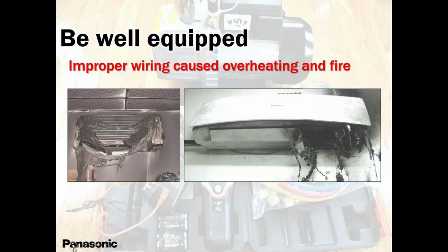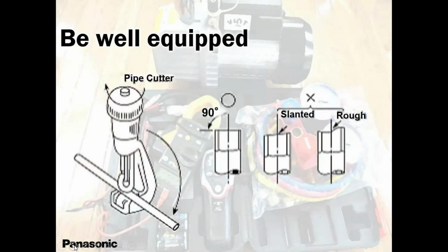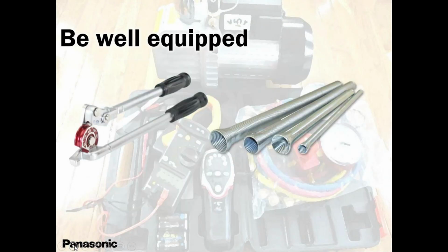Then always use your spirit level. Spirit level is so important, guys. It's a simple tool, but it does a lot of things. When you're mounting your outdoor unit, make sure it's nice and level, or else the oil is not going to get back to the compressor because it's kind of trapped, you know. And then you lose a compressor in less than 2 or 3 years, when the compressor is supposed to last for over 10 years, guys.